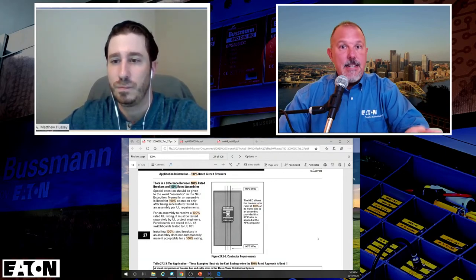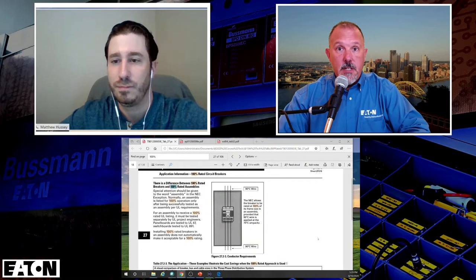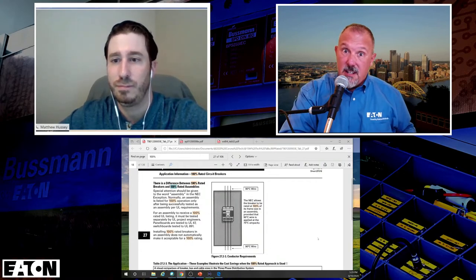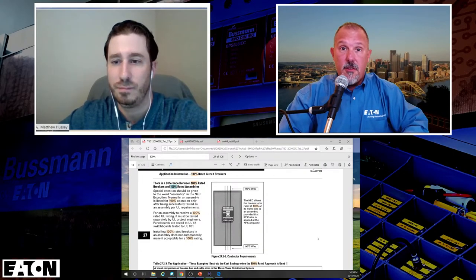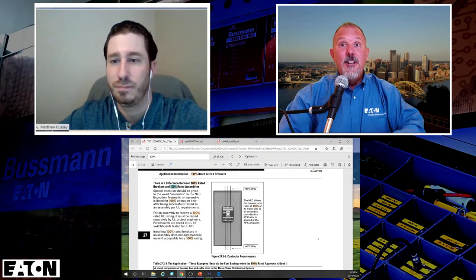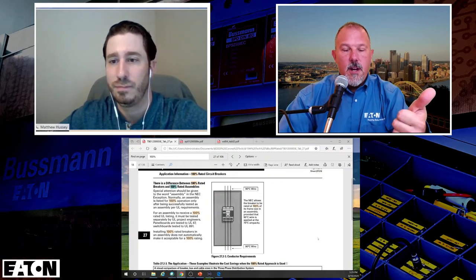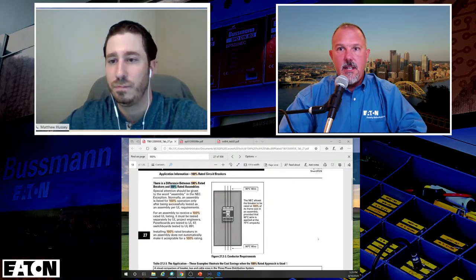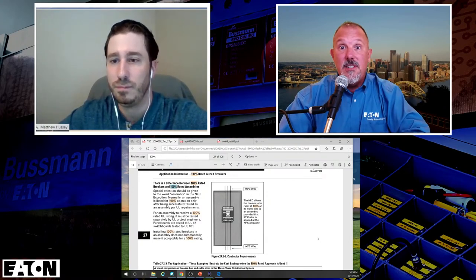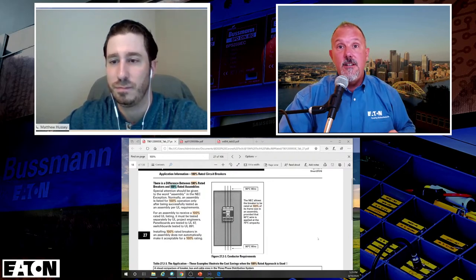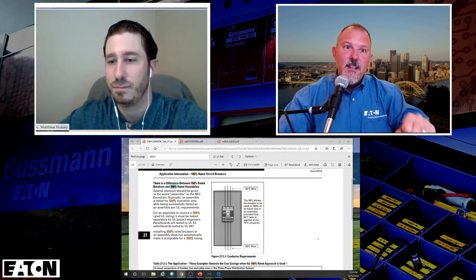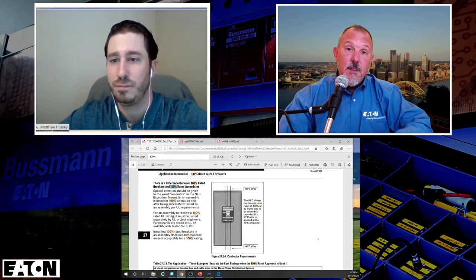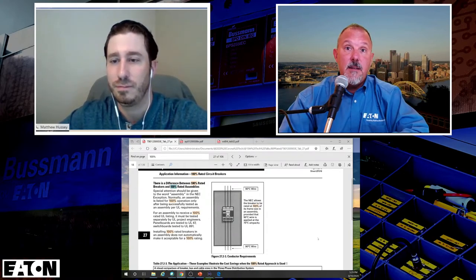75 versus 90, same thing. When I go to a 90 degree C column, I'm going to use a smaller conductor because I'm going to put more current through it at the 90 degree C rating. So for the temperature rating of the conductor for ampacity, I can use 90 degree C insulation, but I've got to use the 75 degree C column, because that's going to make me pick the right conductor for the application, which is going to be thick enough to act as the heat sink that we need when we test that assembly for heat rise.